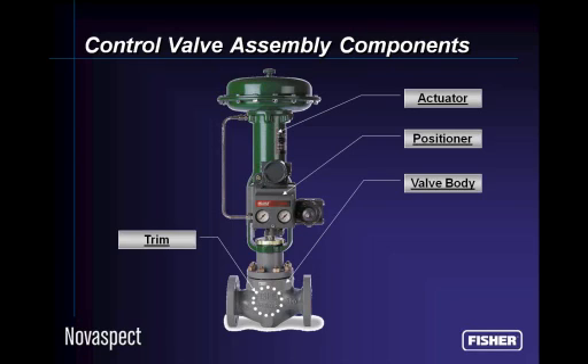Many control valves, not all, but most control valves also have another device called a positioner. These could be electronic, could be pneumatic, they could be field bus. But the positioner's responsibility is to receive the input from the controlling system that tells it how far the valve should be open, and it actually gets valve stem feedback, so it knows what position the valve is actually in, and it continues to run a little control system within that adjusts the air pressure to the actuator so that the plug ends up in the position that's commanded by the control system. And of course, that signal is designed to achieve the pressure downstream that we wanted, P2, in the last slide.